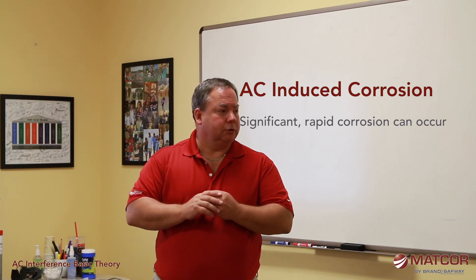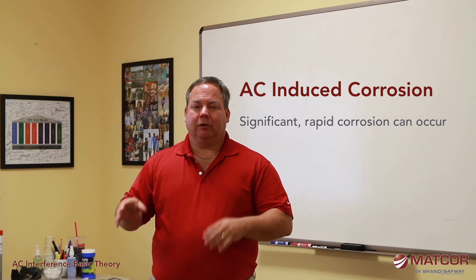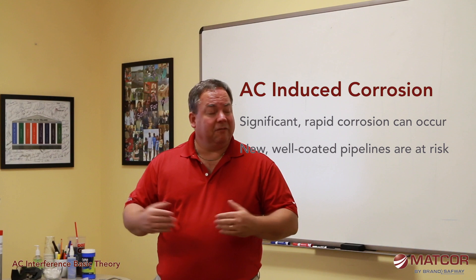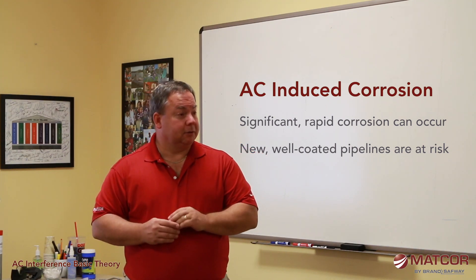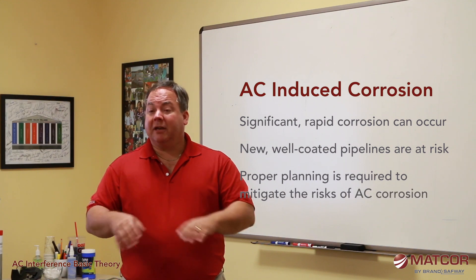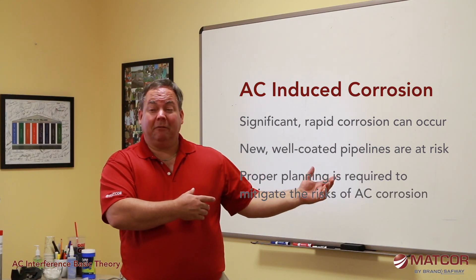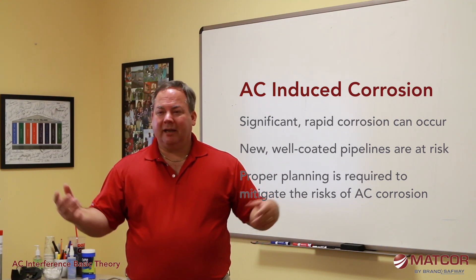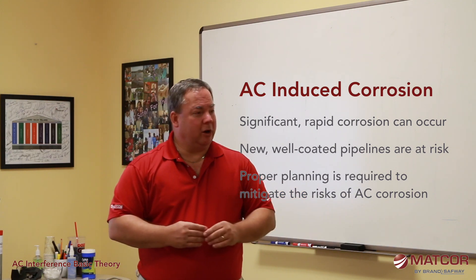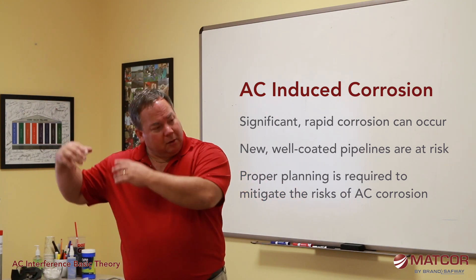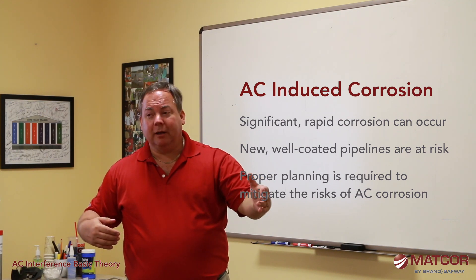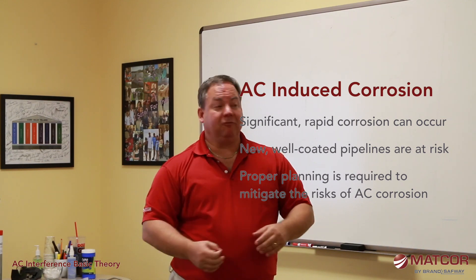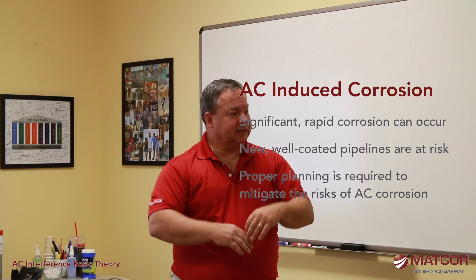You can get very significant, very rapid corrosion from AC induced corrosion. We've had operators with brand new pipelines that within the span of a year have seen significant enough corrosion that the integrity of the pipeline was at risk. The old coating systems had so many defects and natural grounding points that any AC picked up just naturally found its way off. Now the coating systems are so good that the AC has nowhere to go — it builds up, finds the one small defect, and that's where AC induced corrosion occurs.